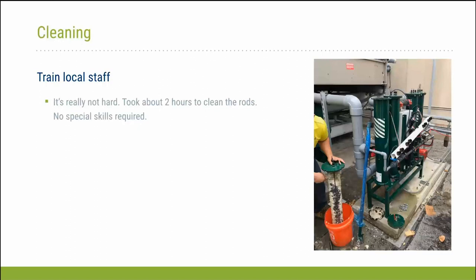Then there's a lid, a plate on the top and the bottom, which allows you to pull that insert out to access the inside of the tube and access the insert where you can remove the mineral buildup. The mineral buildup has the consistency of wet sand for the most part. Your mineral buildup might be different because it depends on the composition of your incoming water quality, but for us, it was very easy to clean. Here the vendor tech was starting to scrape it off with just a pocket knife.